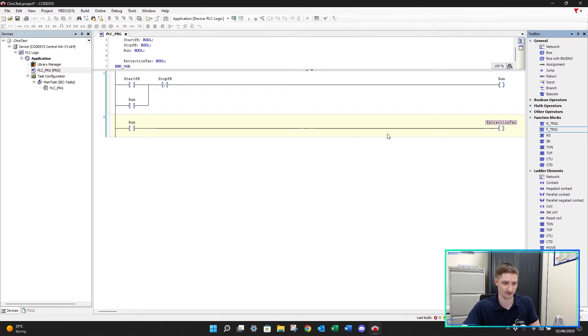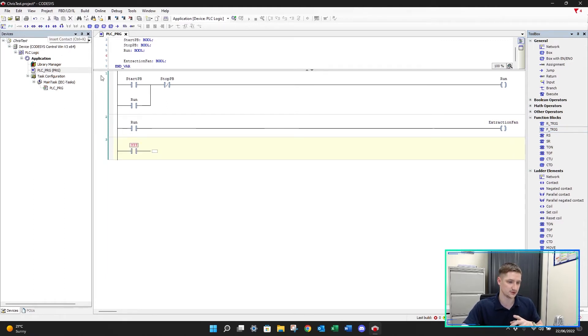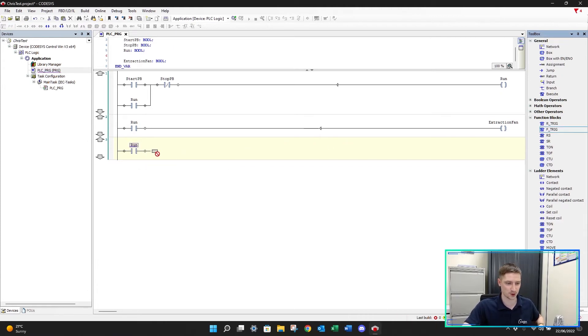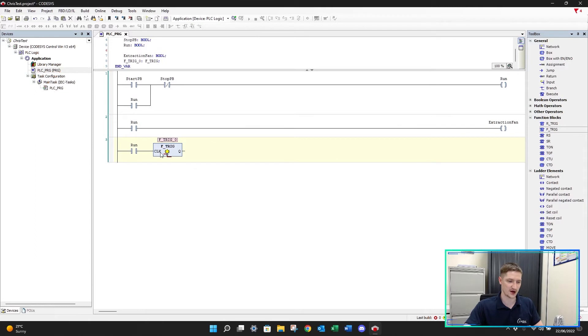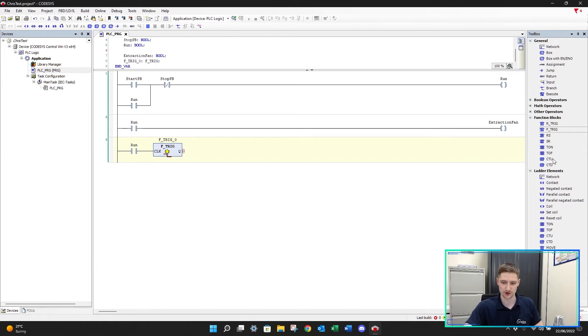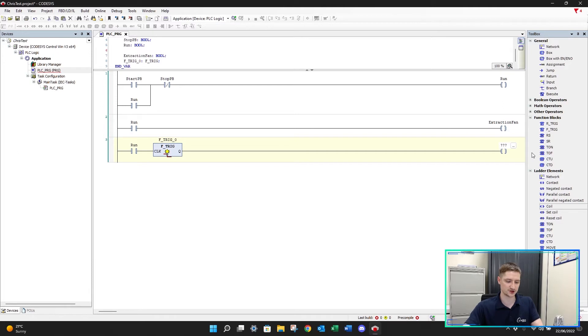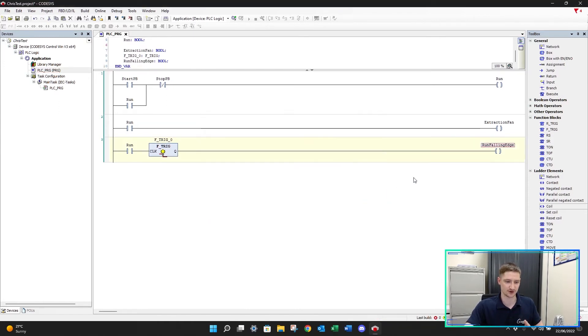I'll create a new network, tie my run signal to a normally open contact, drop in the F_TRIG and give it a variable name. The output of the F_TRIG will turn on for one PLC scan when my run signal turns off. I'll take a coil and drop that in, and we'll call this 'run falling edge' - so this is detecting the run falling edge.